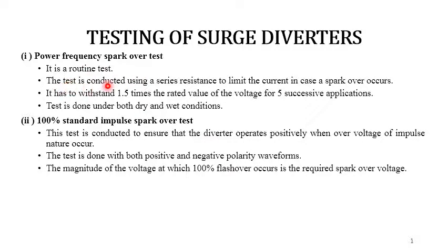This is conducted using a series resistance to limit the current in case a spark over occurs. It has to withstand 1.5 times the rated value of the voltage for 5 successive applications. This can be tested under both dry and wet conditions. Then next we have the 100% standard impulse spark over test. This is conducted to ensure that the surge diverters operate positively when an overvoltage of impulse nature occurs.